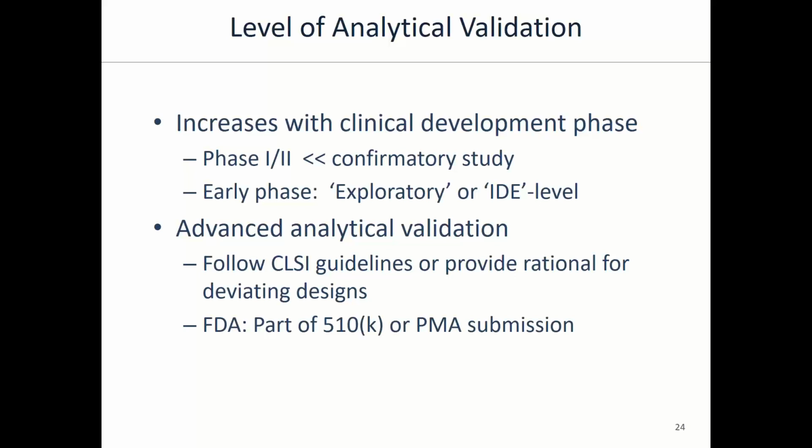I want to point out, and I think this is very well known by the assay developers, but maybe not by the people involved in the drug development process, that this analytical validation result is a substantial part of your FDA submission package. So it's both the analytical and the clinical validation results that will be really scrutinized together by FDA, and it's by no means something that is done in the lab and stays in the lab.